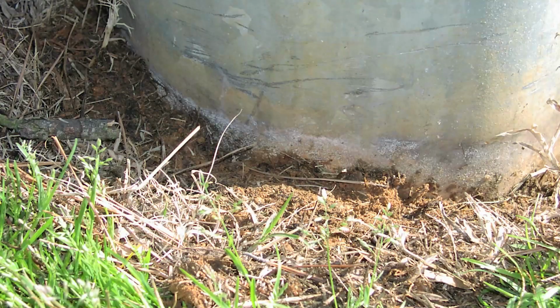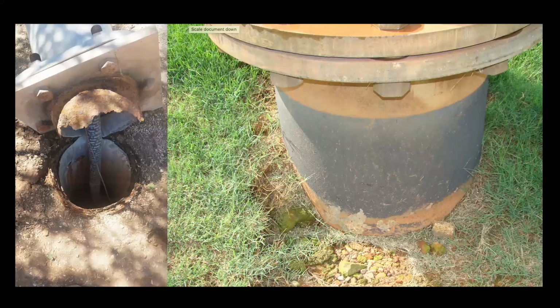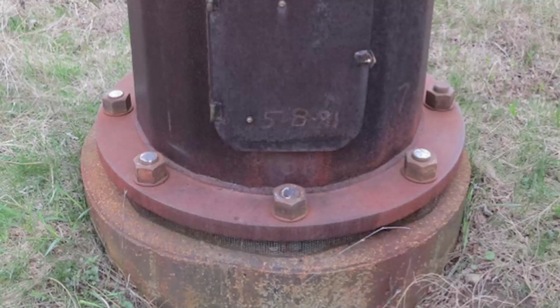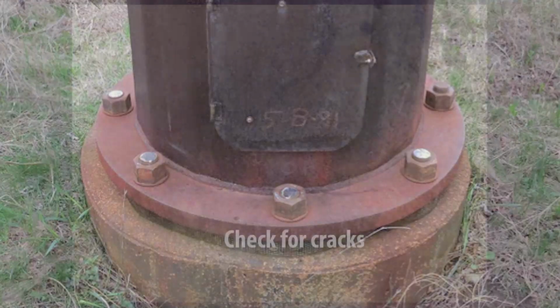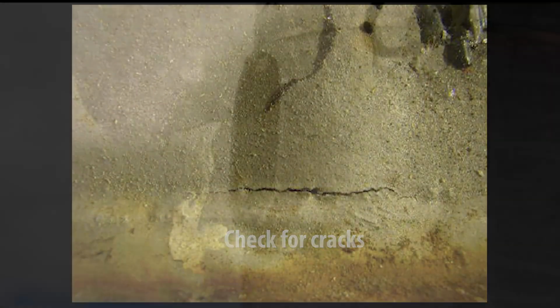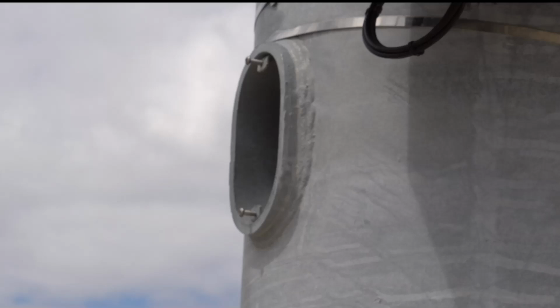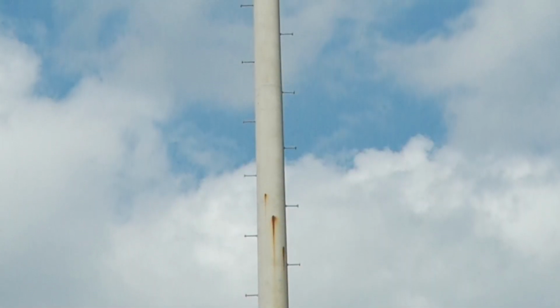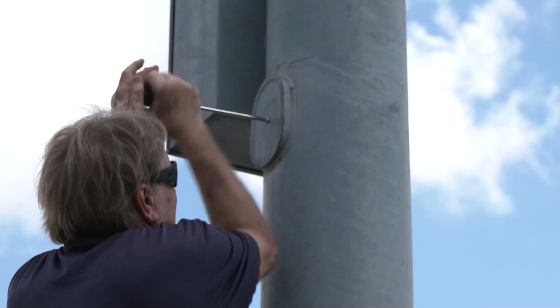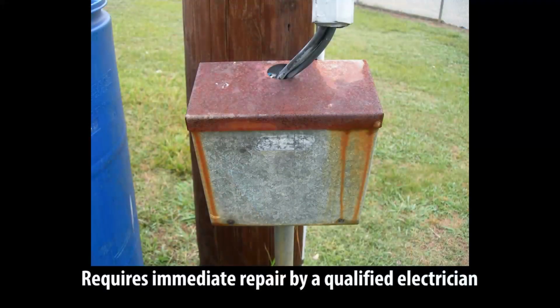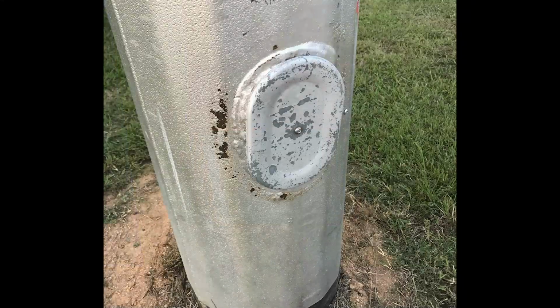For your visual inspection, there are a number of components that you'll want to focus on. Check for any signs of corrosion or rust bleeding on the mounting arms, pole shaft, base plates, and anchor bolts, depending on how your poles have been installed. You'll also want to inspect welds and wire access openings for corrosion, rust bleeding, or other signs of metal fatigue. Try turning nuts to check for looseness. Make sure external cable conduits aren't cracked or missing, and make sure all the pole's electrical access covers are in place.